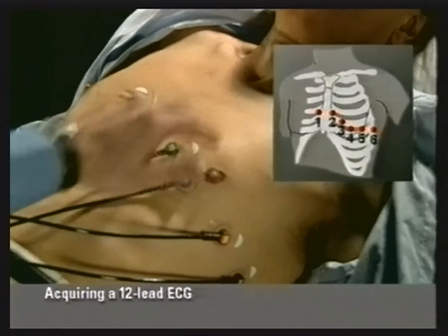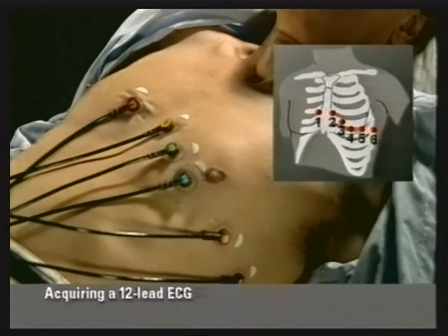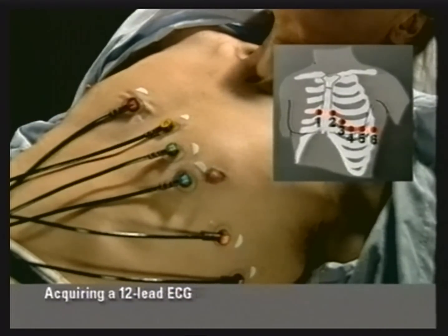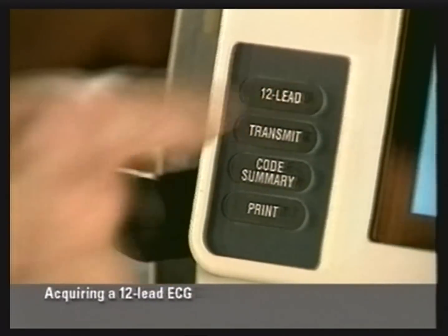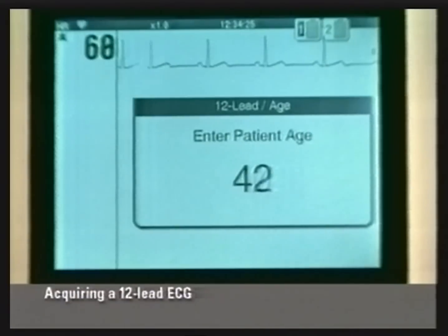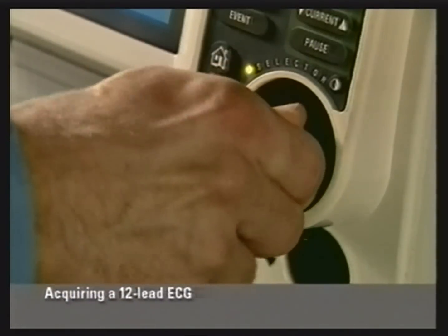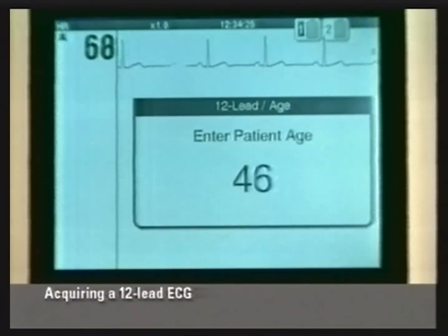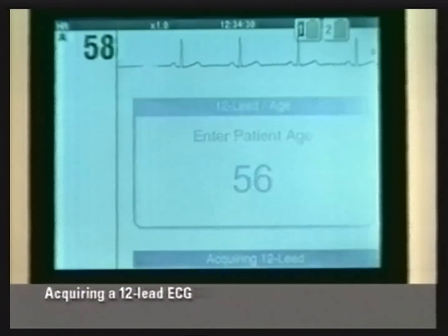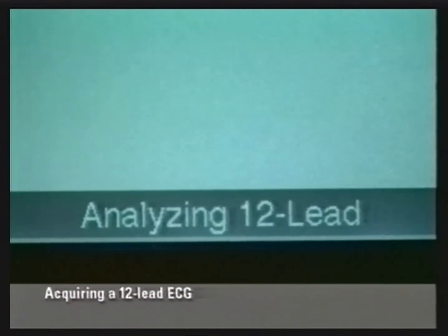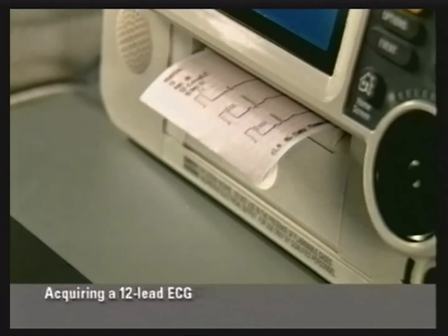It will take a minimum of 10 seconds for the monitor to acquire a 12-lead ECG. Press the 12-lead button. The 12-lead age menu appears. Enter the patient's age with the selector. If an age is not entered, the 12-lead automatically selects 40 and begins acquiring the 12-lead ECG. The monitor acquires, analyzes, then prints the 12-lead ECG.